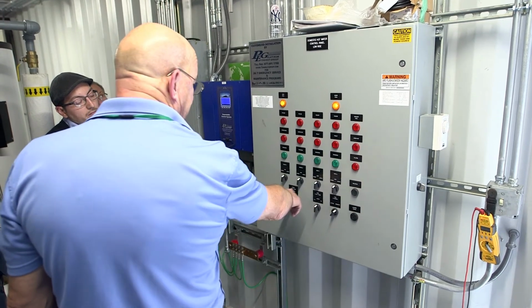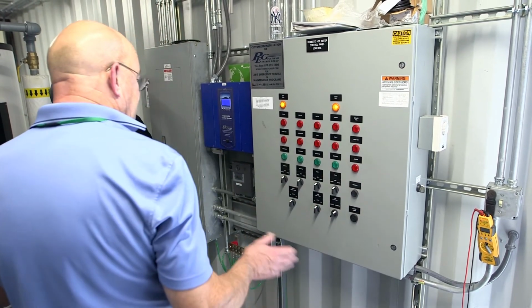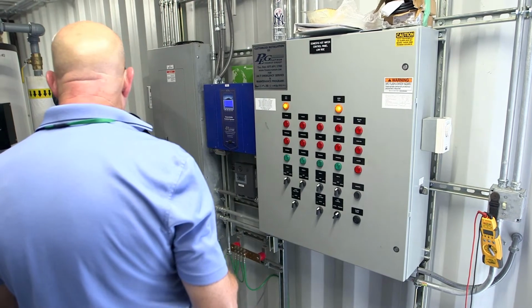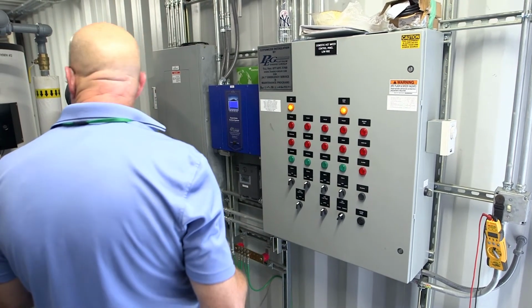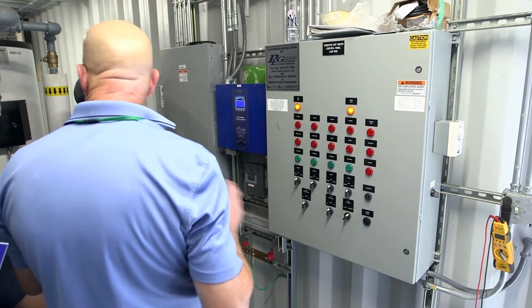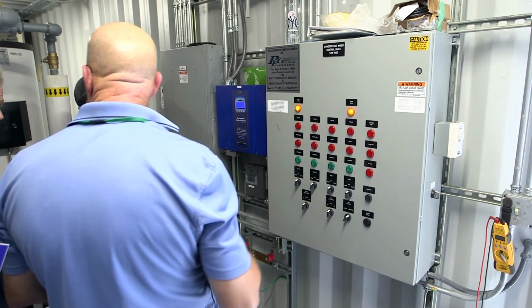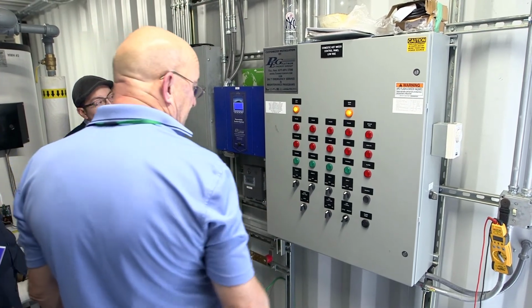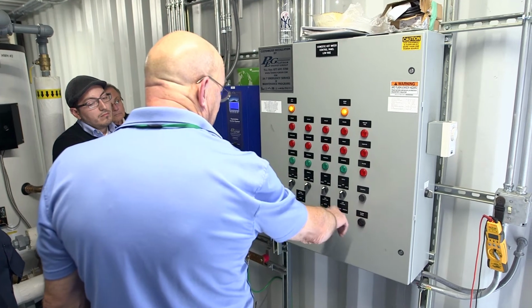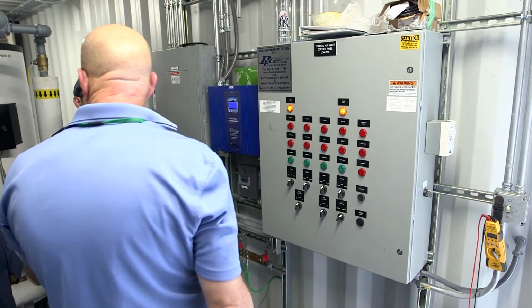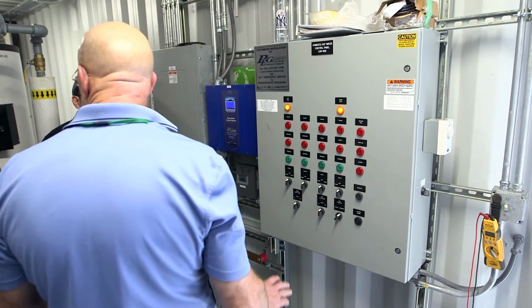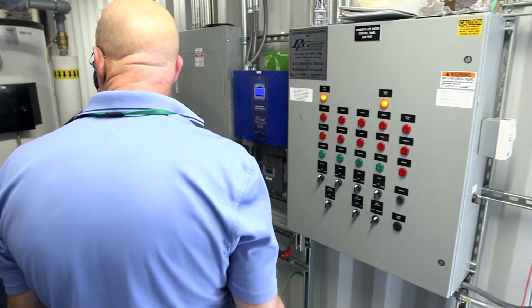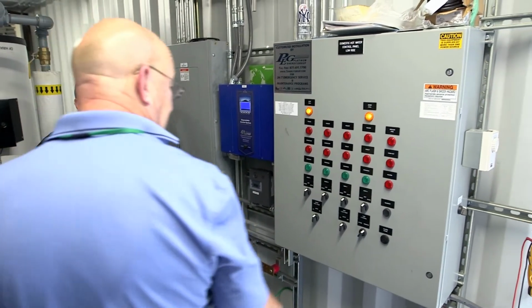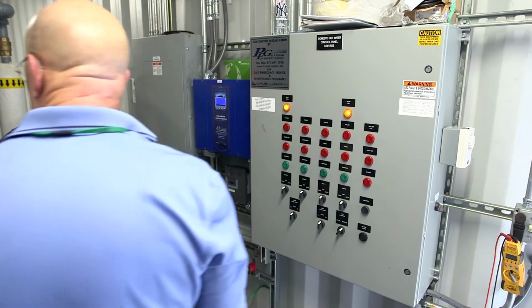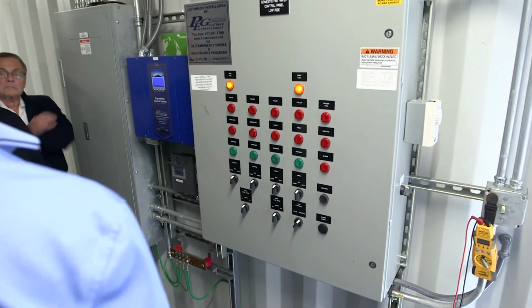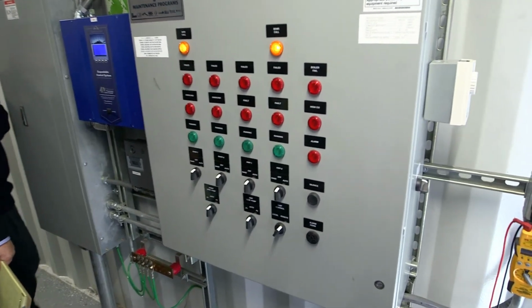These two. It says domestic hot water lead pump. If they want 1 to run all the time or 2 to run all the time, you want to let it do it automatically on its own so it cycles. Let it vary. The hot water pump control is remote. Remote means something's calling for hot water and it's going to run. If it fails, you can go to local control and it'll run local. There's no reason you can't.